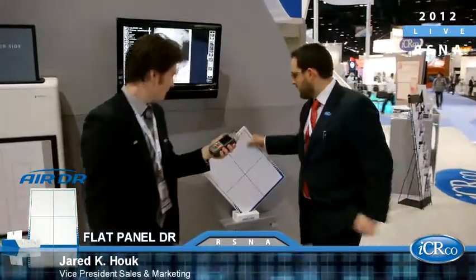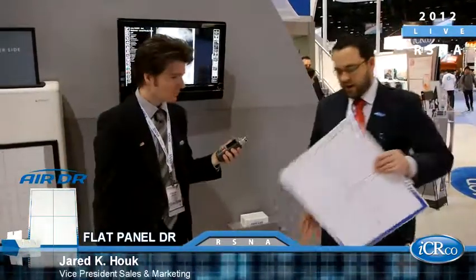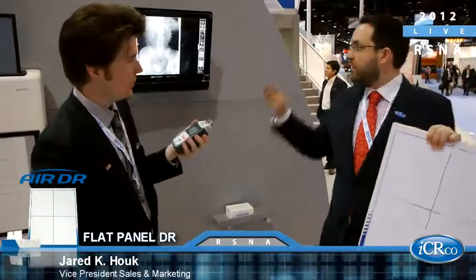This is called the AirDR — iCRco's wireless flat panel detector. We're pleased to introduce our wireless DR panel, cassette-sized 14x17. It has the ability to automatically acquire images and send them wirelessly to a workstation. This is a CsI or cesium iodide-based detector. It's 2.8 kilograms, the lightest DR panel on the market, and has the ability to acquire images in three seconds.